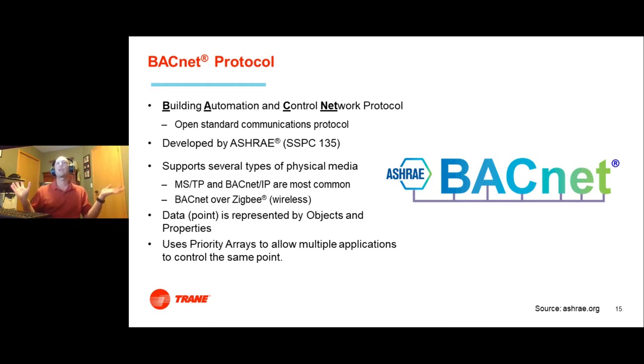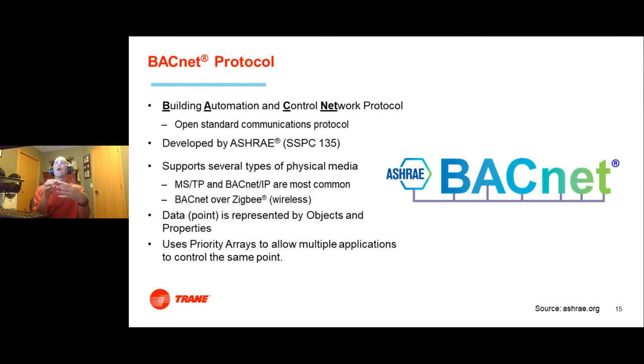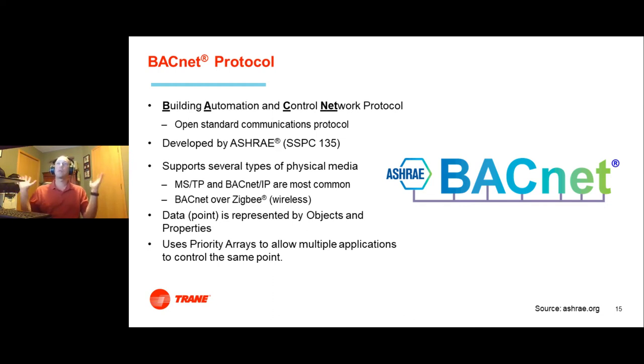One key thing BACnet has that other protocols don't is what's called priority arrays. If I want to control a specific point, like a setpoint, I can have multiple vendors or multiple applications control that same point — the highest priority wins. When I release that highest-level priority, the point still remembers all lower-level priorities and uses the next highest. This is really conducive to having an open system, and it's a feature you don't often see in other protocols.